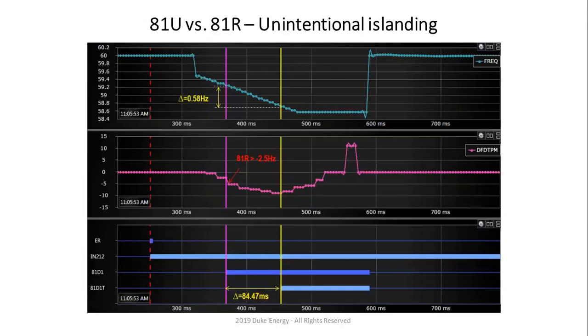So you can clearly see that 81R goes below a negative 2.5 hertz almost immediately after the 81U, or under frequency, picks up, right? Now, that means that the 81R scheme over here would be faster by close to 80 milliseconds. But remember, certain things happen on the feeder, and just because 81R detects, you can't just go over there and say, oh, I'm going to initiate islanding right now, because it might be one of those transients. So in order to increase the security of the scheme, this 81R setting has to have some kind of time delay. So we have taken a time delay of 2 cycles to be enough so that we take out all of the transitions that are actually resulting in some sort of unwanted islanding, where it's just some kind of temporary fault or something like that, right?